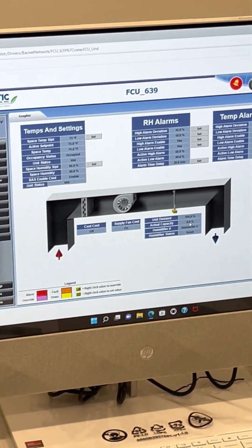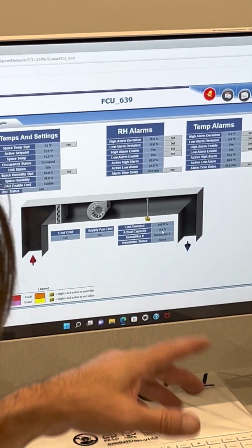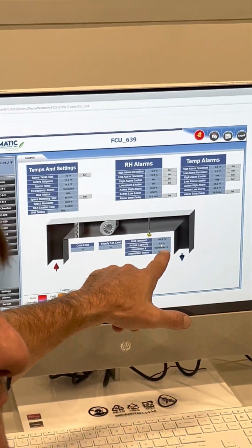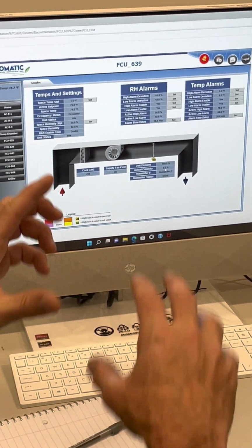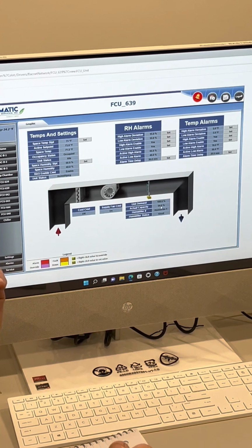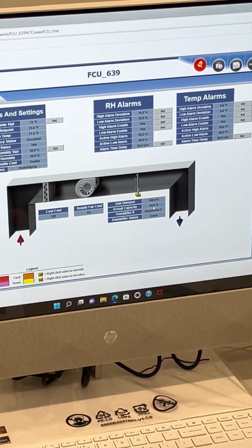They can tell by the BTUs per pound an hour of what they're generating. You'll see it a lot at 100%, 90%, but your actual capacity only at like 40 or 50. That's all part of the humidifier on how it does it. I can't change that or do anything with that. It's based off a set point and how far out of deadband.